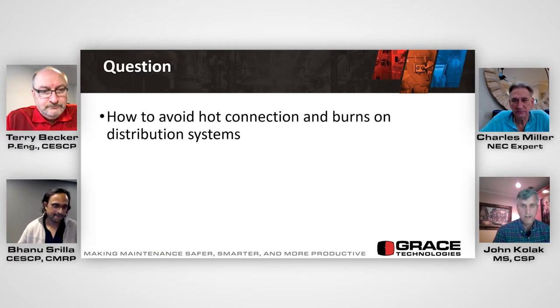Hot connections usually are a function of resistance, caused by an incorrect or improperly made connection. So improve and clean the connections, use the right kind of connectors, pressure squeeze-down connections preferably. That'll help with hot connections or burns on distribution systems.